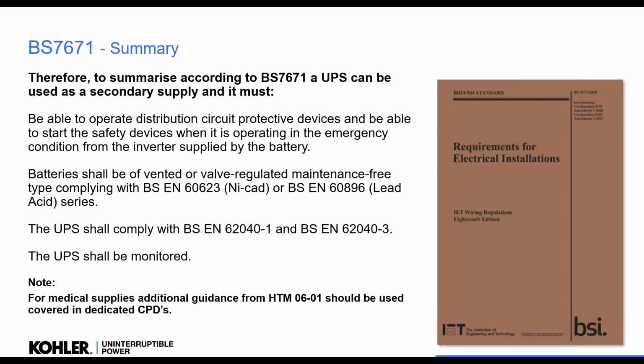So to summarize, we can use a UPS as a secondary supply. It must be able to operate those downstream protective devices, start the devices on battery with no mains, batteries to the relevant standard, UPS to the relevant standard, and monitored. Obviously, for medical supplies, we have the additional parts in 7671, and also for healthcare, we have the HTM 0601, which tends to follow the 7671 in a lot of ways.